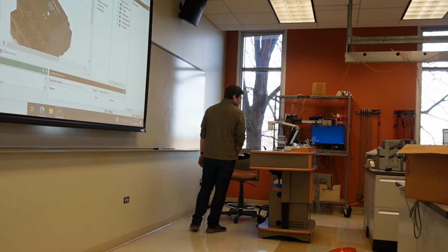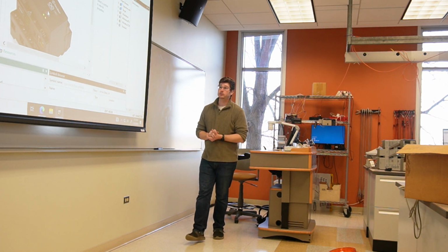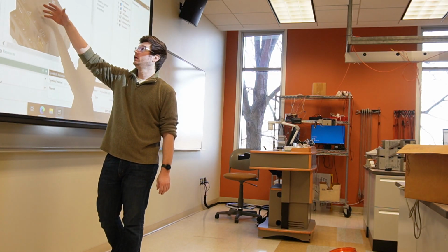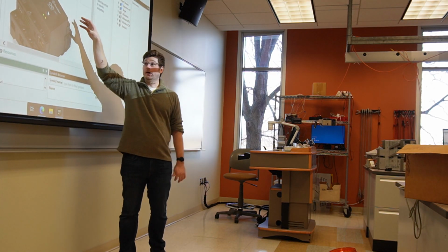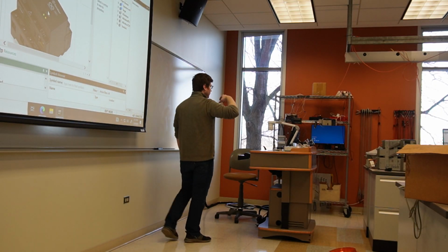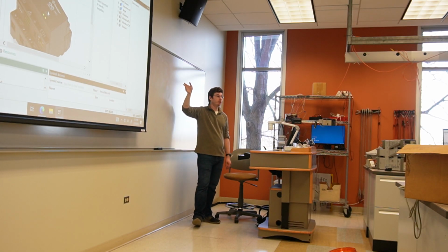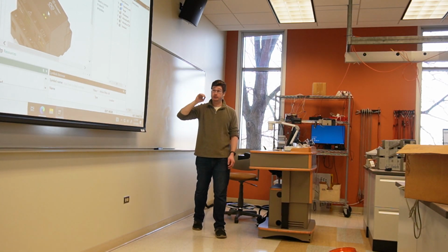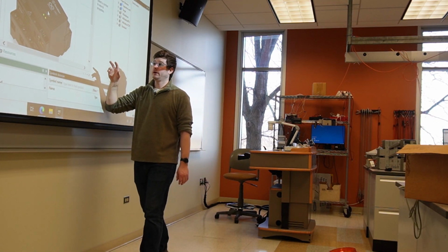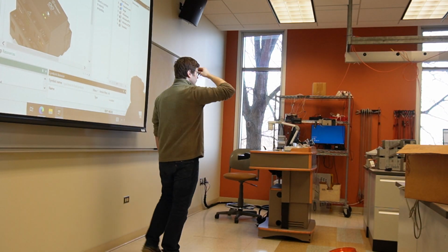For the record, the USB-C does power the device. It allows us to upload code to it. It allows lights to blink, right? We have some indicator lights that are useful for us, user controllable and otherwise, but relays will not click, okay? We need 12 volts. We need the PLC to be powered on its terminals for the relays to actually click over, okay? So just keep in mind that we can upload code to it, but if you're trying to get a relay to click and you don't quite know why, it could be that you aren't actually powering your PLC if it's just powered through USB. Okay.